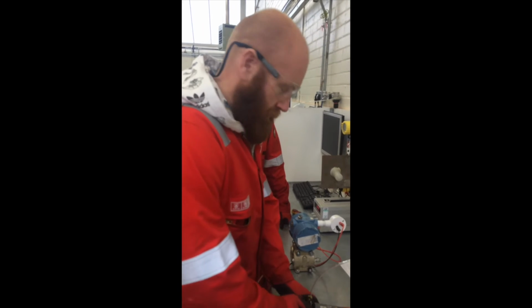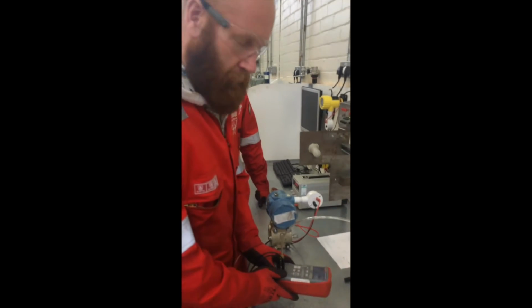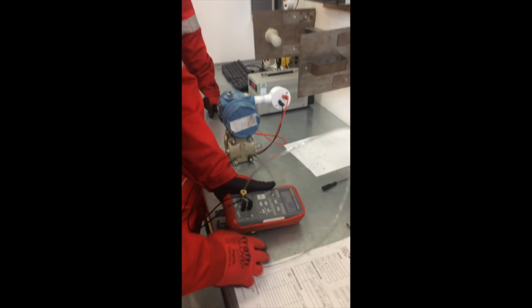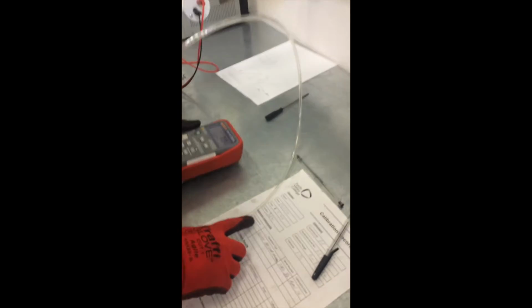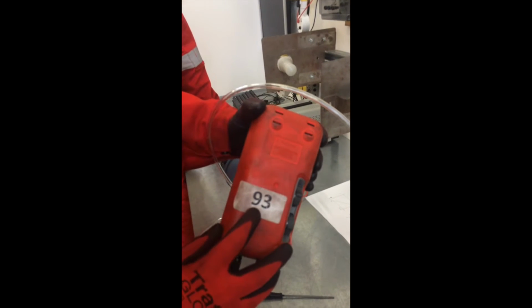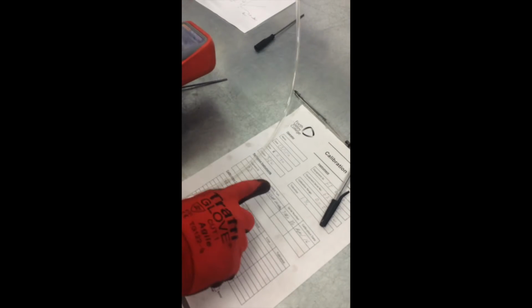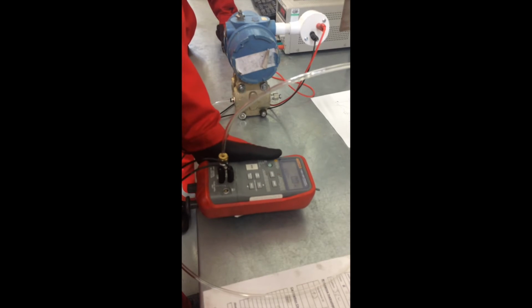Before doing the calibration, we need to take some information about the instrument we're using. So we're looking here for equipment ID, which we can find on the back here, it's number 93, so we write that down. The type of equipment we're using is a Fluke pressure calibrator, so we've got that written down here. The serial number for the pressure calibrator is along here, so write that in the box, and the calibration date for the pressure calibrator is along here, stuck along the side. So we're just taking a note of that again.